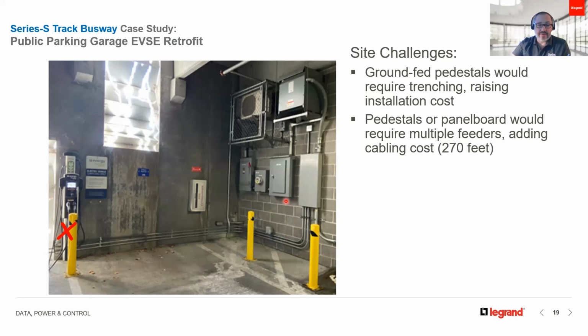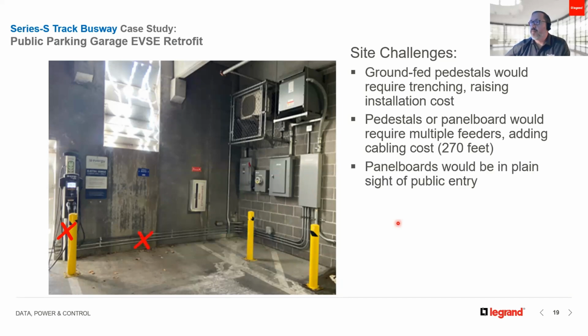So your panel is a load center at a residential level. Here we're talking about a panel board for commercial application—same thing, just bigger. But what happened is that when this system was created, it wasn't designed to have provisions for such large electrical loads, like electric vehicles on ramps in this case. So the panel board only has room for a certain number of circuits, and if you don't have enough room to add a breaker, or the right amperage, you have to add another panel. In this case study, that would have meant adding more panels and more of these bollards.